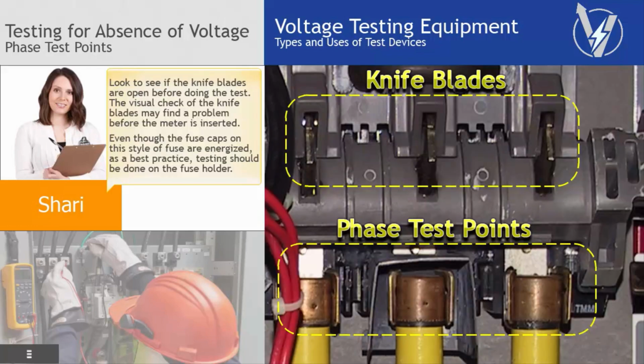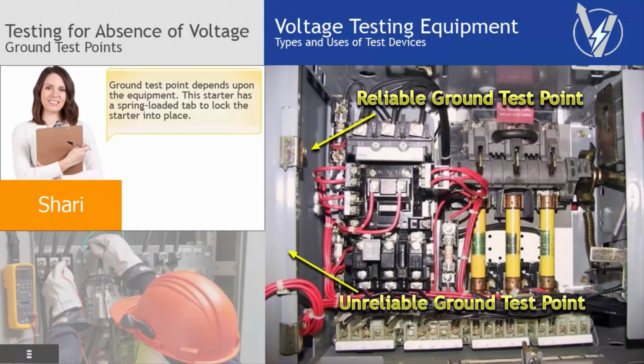Look to see if the knife blades are open before doing the test. The visual check of the knife blades may find a problem before the meter is inserted. Even though the fuse caps on this style of fuse are energized, as a best practice, testing should be done on the fuse holder. Ground test point depends upon the equipment. This starter has a spring-loaded tab to lock the starter into place.